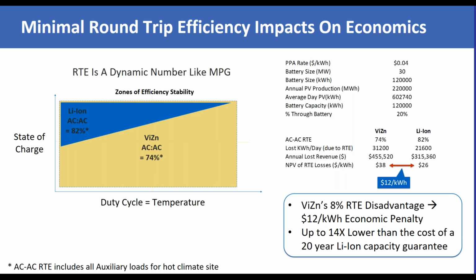So let's take a look at what that means for this actual system. Starting at the top, 30 megawatt system, 4-cent PPA rate, 120,000 kilowatt hours into the battery, and an annual solar production that's on a daily basis 602,000 kilowatt hours. So for a single cycle, only about 20% of the plant output can go through the battery, right? If we consider round trip efficiency losses as lost revenue, lost kilowatt hours per day, the ViZn system loses about 31,000. The lithium-ion system loses about 21,000.